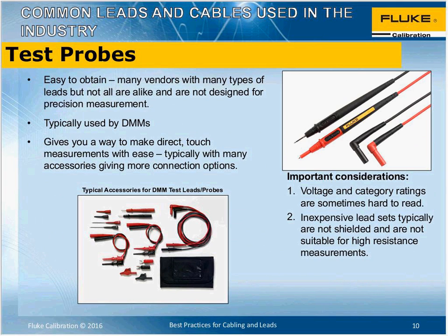Probes, we're not going to cover too much on test probes today, but I did want to note that they're easy to obtain and very common. The one thing here is, not all test probes are the same. When you do your research, you could run to Home Depot or wherever your local electronics store is and get a pair of test leads, no problem, and they'll do the job. But just know that there are high quality test leads out there, some with higher safety protection features, such as the Fluke here that has the shield that retracts, and you can also retract that shield by turning the tip of the lead.